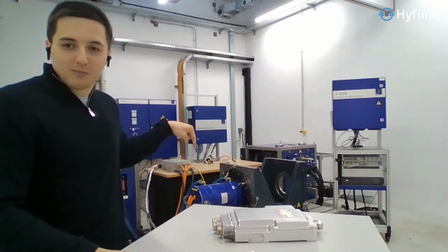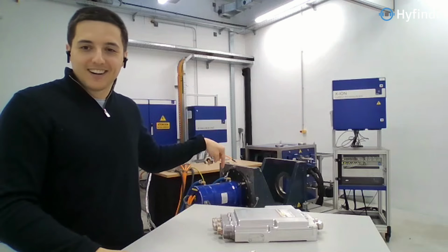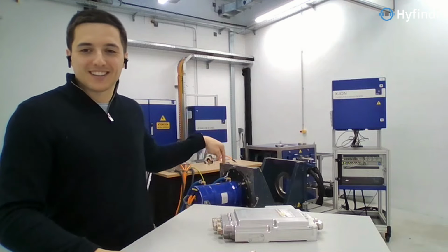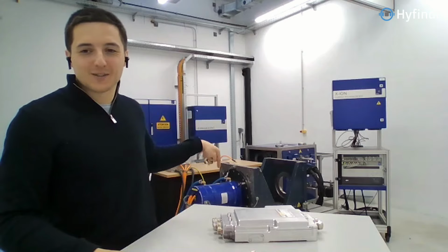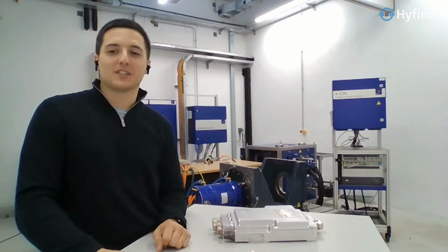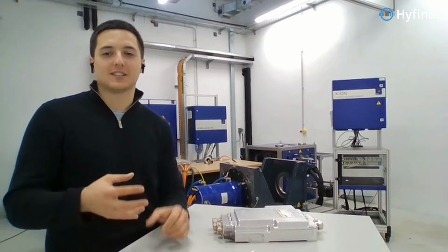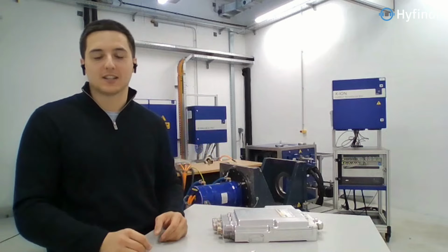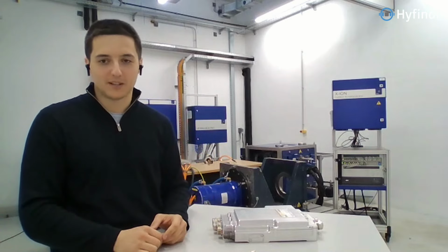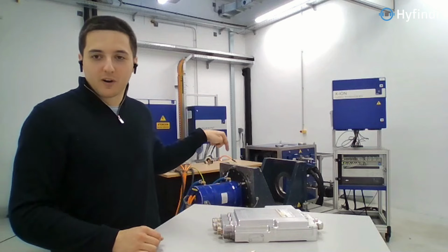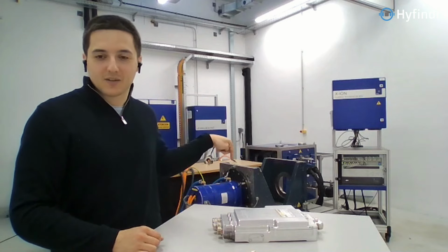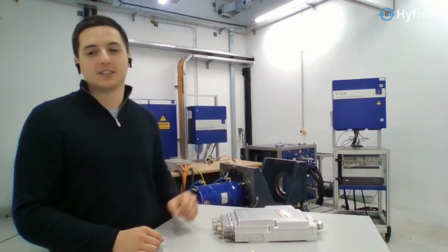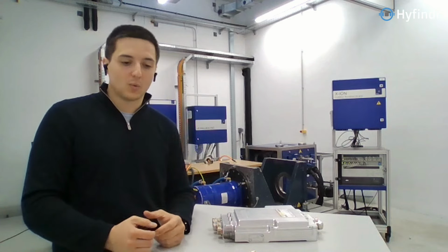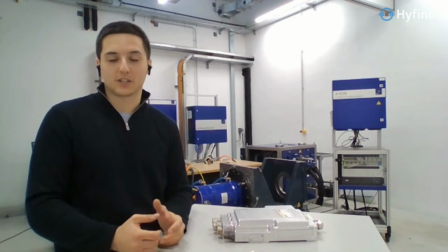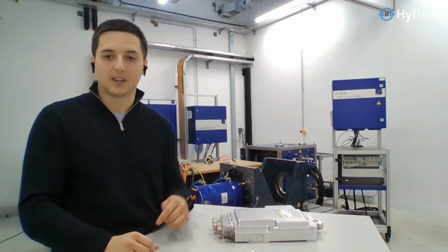Let me point it out. I think it's here. Yes, correct - this blue motor is the dyno, the brake dyno. It generates the brake torque, braking the unit under test, which is the motor we want to calibrate. Following this line in the middle, there's a shaft with a torque sensor - a device that measures the torque on the shaft, the torque the motor is generating.